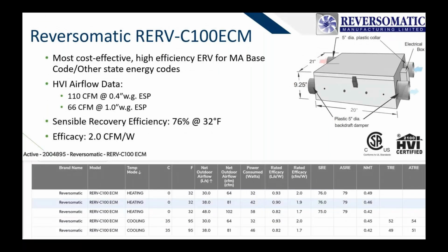So, kind of branching out of the passive house design criteria right now, this wouldn't necessarily, technically it would work because you're at 76% SRE at 81 CFM, but usually the CPHC likes to see a little bit more SRE than that. But it really would work very well for either Mass Base Code or other state energy codes. The HVI airflow data here is not as robust as it was before, but again, this is a very cost competitive option, and would work well as a substitution for many ERVs that are outside the passive house design criteria. 110 CFM at 0.4, 66 CFM at 1 inch, and again, 76% SRE at 32 degrees, and then decent efficacy of 2.0 CFM per watt.